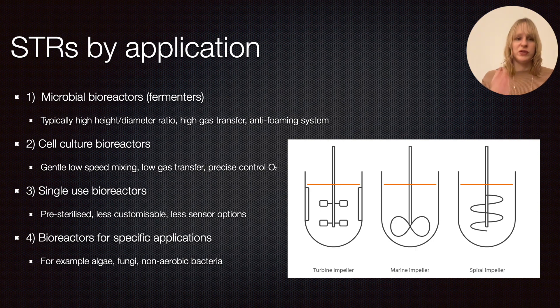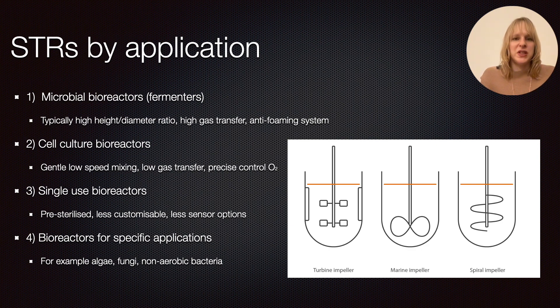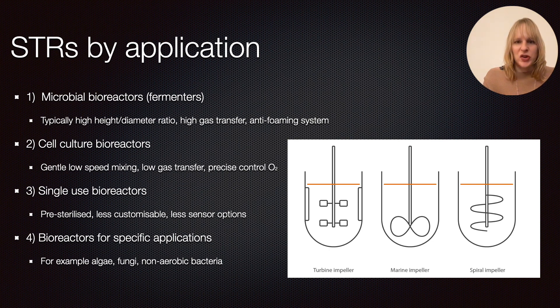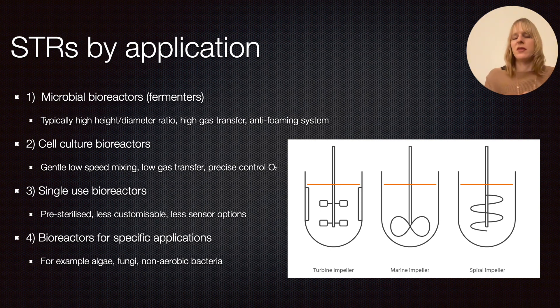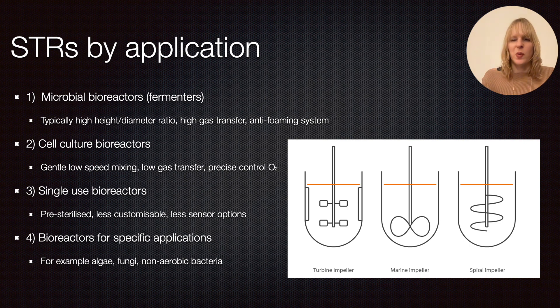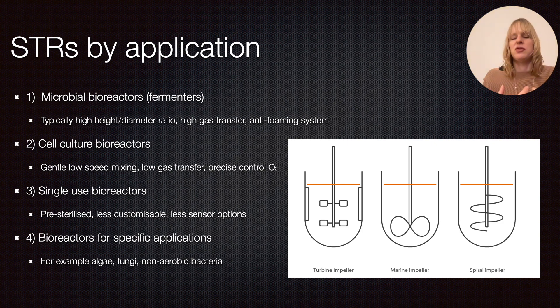There's also the option of single-use bioreactors. These are pre-sterilized, which avoids contamination, and they are quite flexible — if you want to make different products you can rapidly switch between them. However, they are less customizable for very specific requirements, and there are fewer sensor options available, making it harder to monitor your system. Generally, single-use systems are used on a much smaller scale.